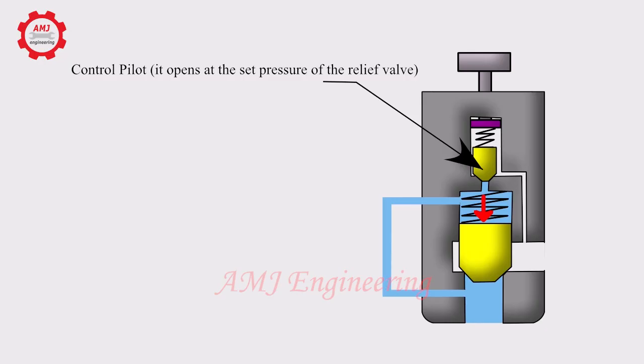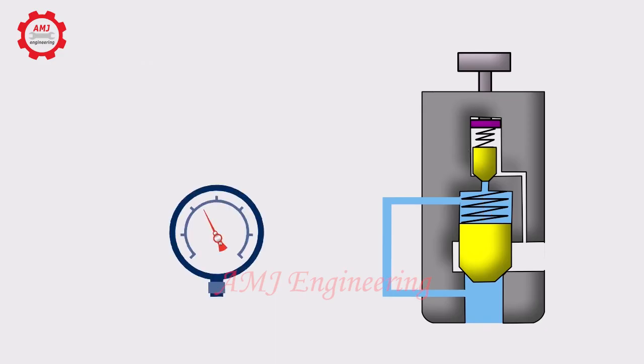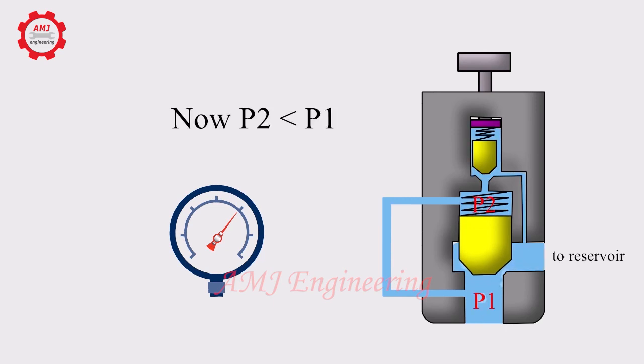The pressure at which the control pilot relieves is the functional set pressure of the relief valve. When the pilot valve reaches set pressure it opens and releases the pressure from the dome. The piston is then free to open and the main valve exhausts the system fluid.